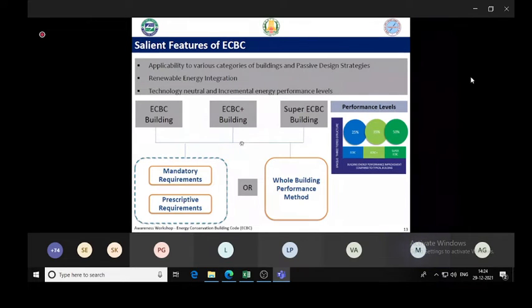Right. And there are 2 compliance methods. In the code, we have mandatory requirements first, which are mandatory for any building. There is no compromise on that. Mandatory requirements in each section. And then we have 2 options: either we can go for prescriptive requirements or a whole building approach. In prescriptive requirements, we need to follow the code compliances to the dot, exactly as per the code. Whatever is stated under the prescriptive requirements needs to be followed. Whereas in the whole building approach, we have flexibility between different code provisions, like between the building envelope and HVAC, between the HVAC and lighting. So we have some flexibility to compensate or trade off between different sections of the code.